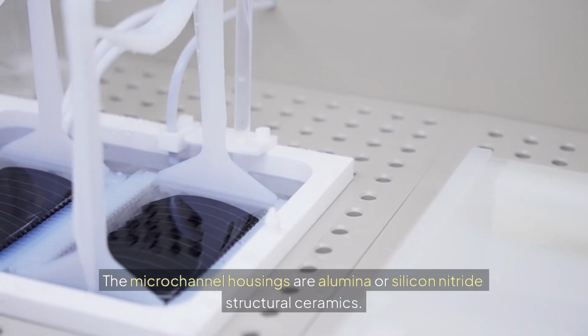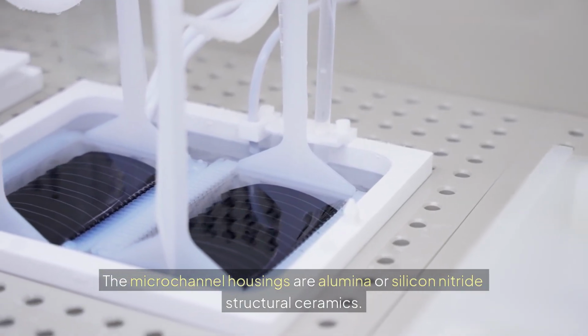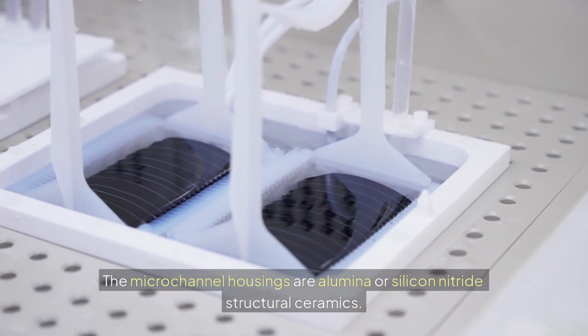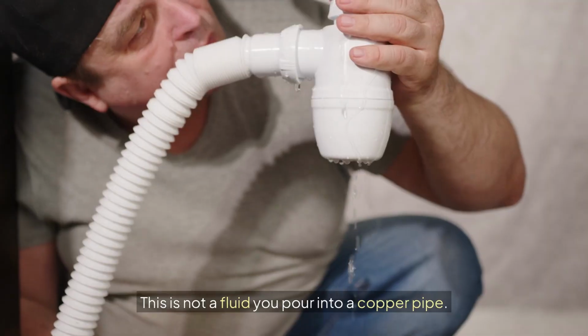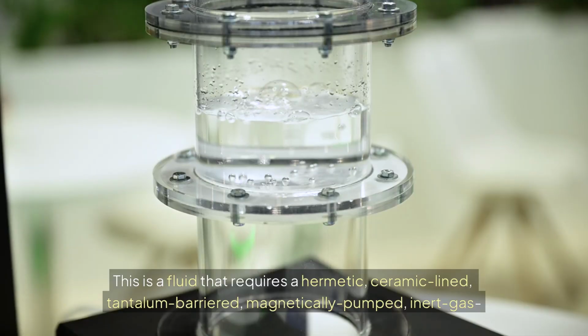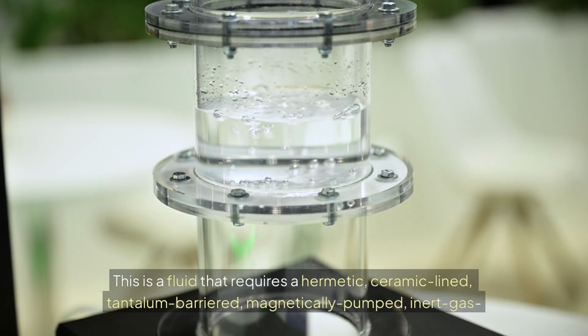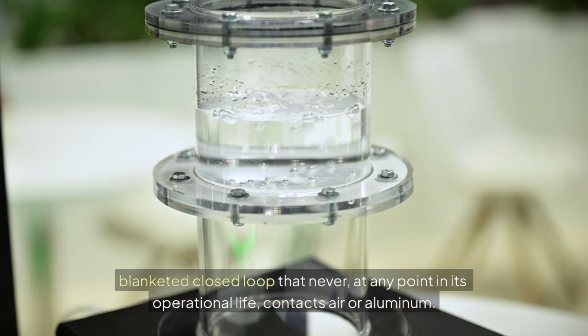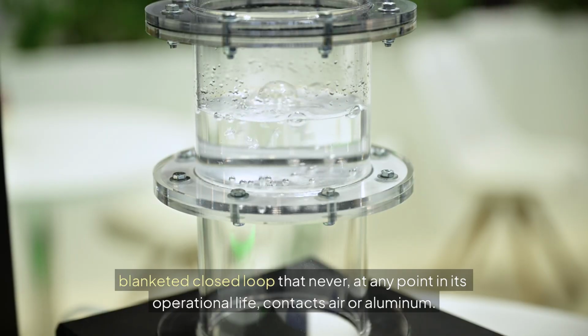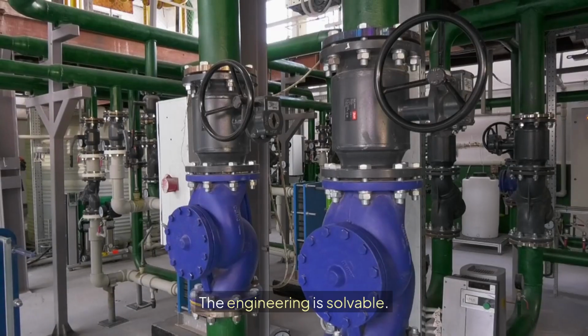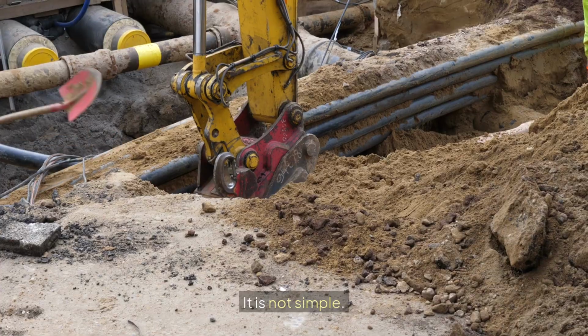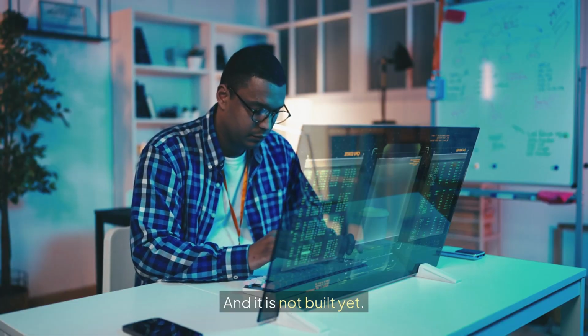The microchannel housings are alumina or silicon nitride structural ceramics. This is not a fluid you pour into a copper pipe. This is a fluid that requires a hermetic, ceramic-lined, tantalum-barriered, magnetically pumped, inert, gas-blanketed closed loop that never, at any point in its operational life, contacts air or aluminum. The engineering is solvable. It is not simple, and it is not built yet.